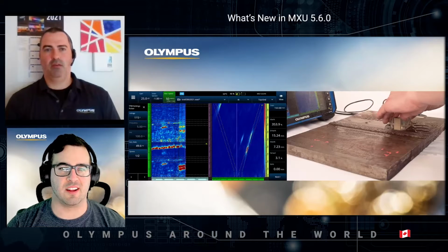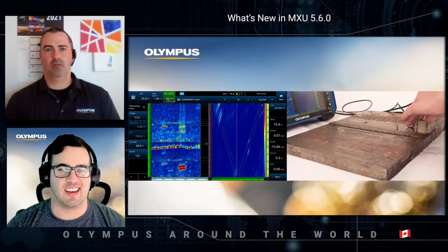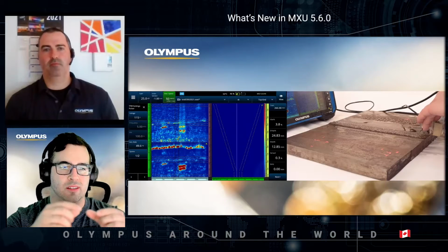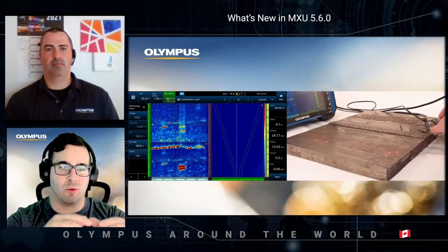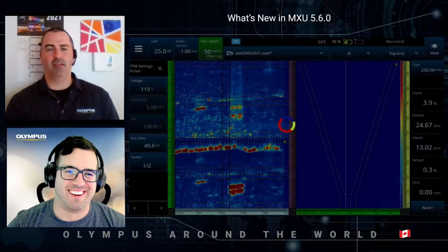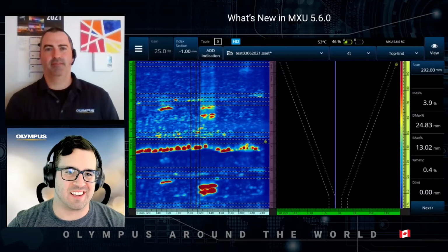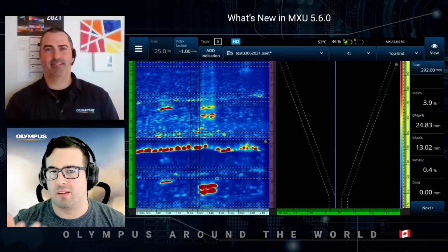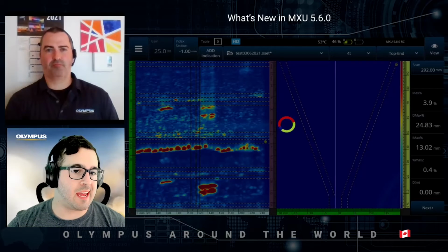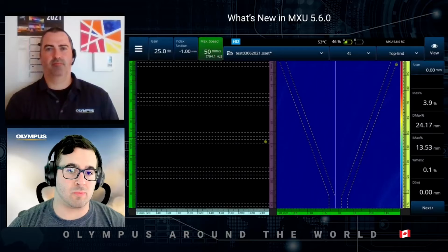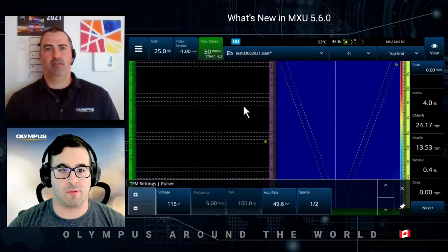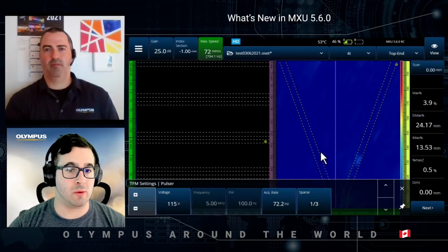So you can see here I scan a little bit faster, but again, I did not do it too slowly. So I am a little bit faster with the hand and have a little less missed data. Yeah, exactly, like the full matrix one. But in terms of result, it's pretty much the same. And again, I would switch that for the next one to 1:3. That means one pulser out of 3 will be used for the acquisitions.